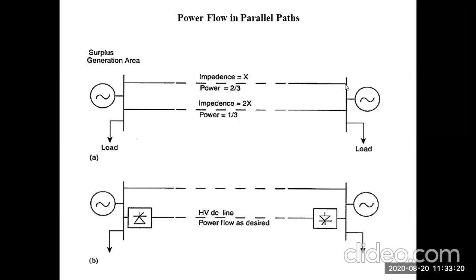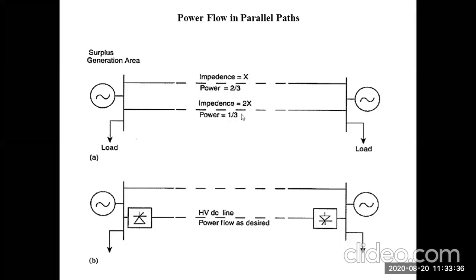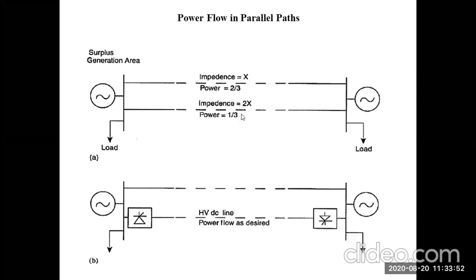In Figure A, if another line has impedance 2X — higher than the first — the power transfer in that line is only one-third, whereas the first line carries two-thirds. This means that as line reactance increases, losses increase. The question then is: what alternative measures can we take to reduce losses and increase capacity?